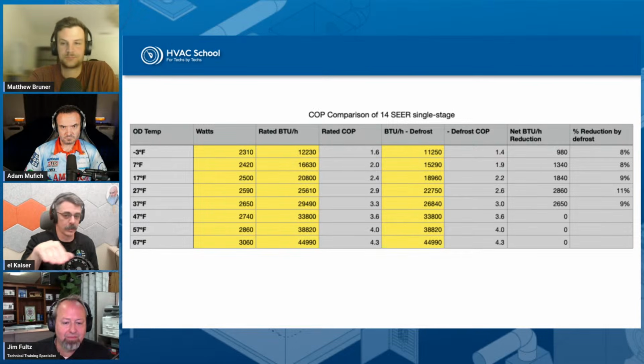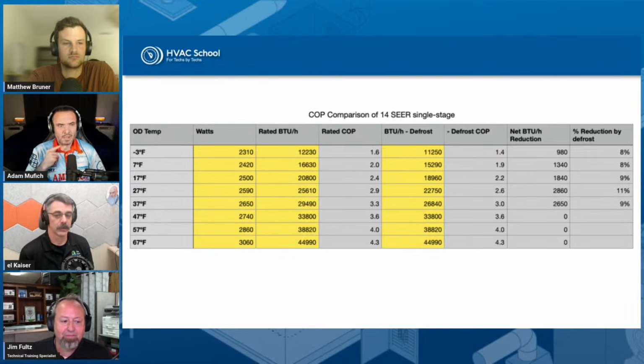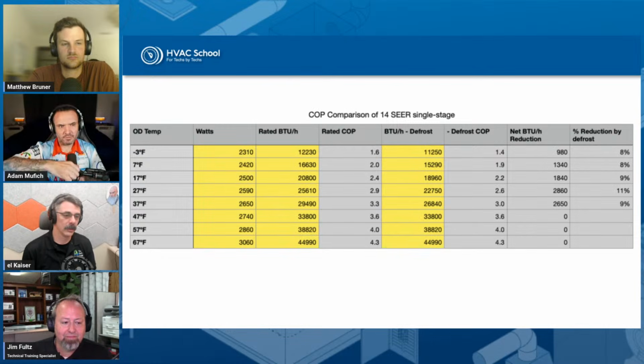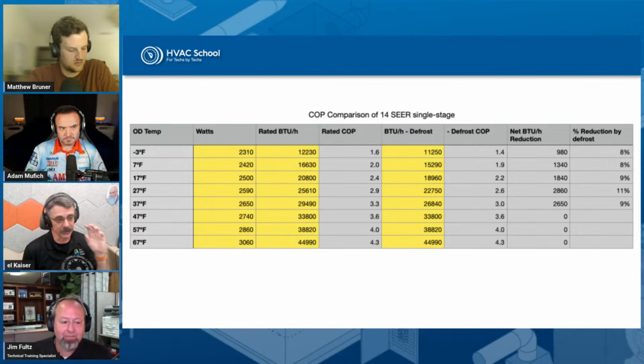And you notice that at 47, we stop getting a reduction for defrost, right? Because we're not really going to see any defrost cycles above that 47 number. But if you look over to the right, the primary reduction from defrost is around that 27 degree mark. And as we go down, we actually lose a little bit of percentage because we're not seeing as many defrost cycles. I'm questioning how accurate this is if you actually have a system with demand defrost, right? Yeah, that's going to vary a lot. This particular one is timed defrost, yes. And to Adam's point, you're going to see typically fewer defrost cycles with a demand defrost.